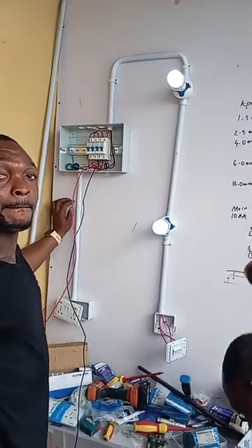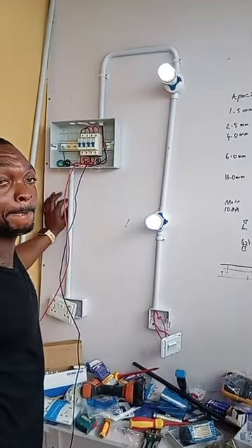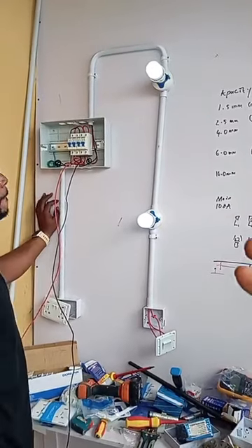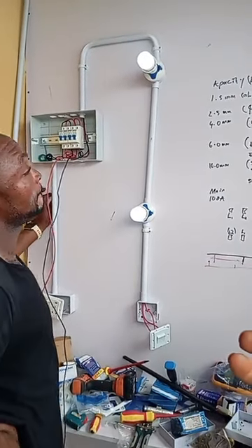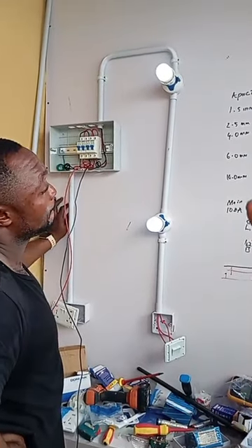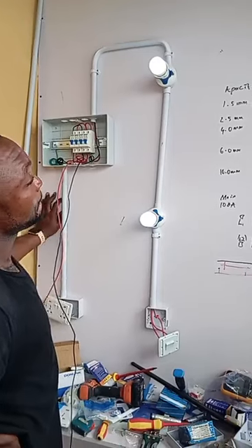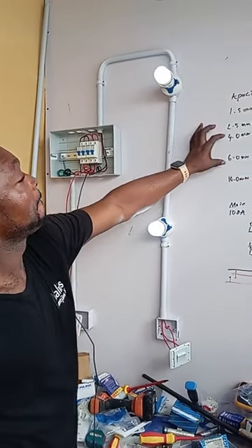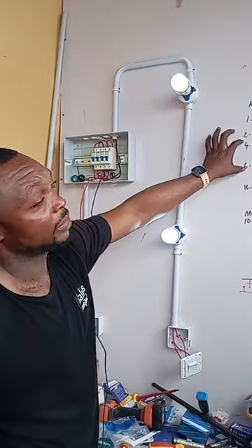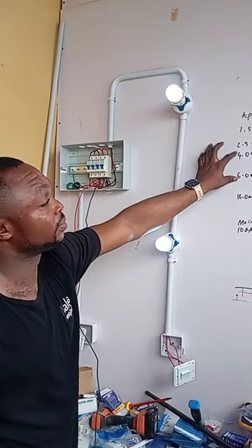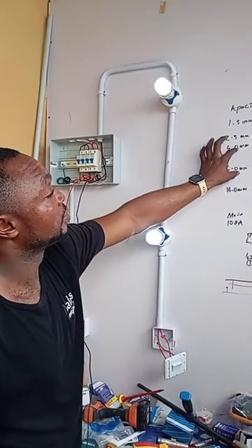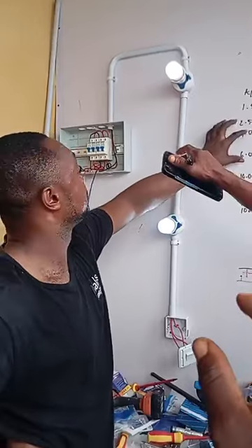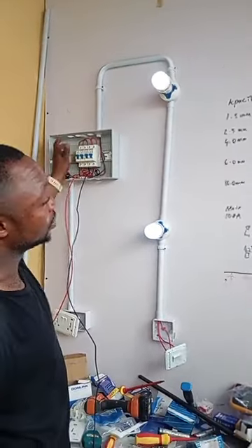So now, if you are doing electrical connections and we have something like AC, water heater, all these heavy appliances, we recommend using 4 mm or 6 mm cable, with a 25 amps breaker or 30 amps breaker.